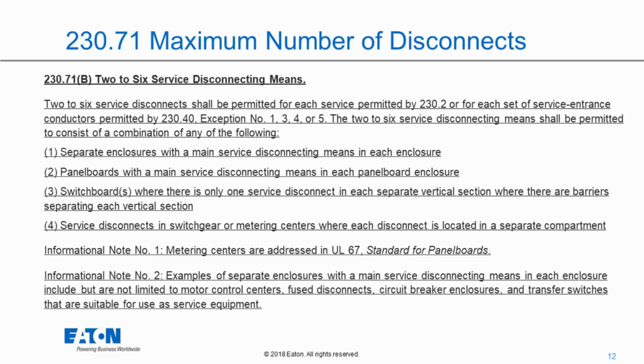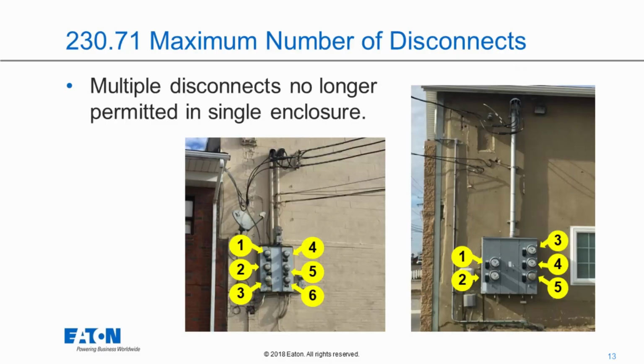And then with regards to list item 1, they give an example of separate enclosures with a main service disconnect. Could be, but not limited to, motor control centers, fuse disconnects, circuit breaker enclosures, and transfer switches that are suitable for service equipment. So this is a very common scenario. I mentioned earlier about the meter centers. It was very common to perhaps just come into a pull section, an incoming terminal box pull section in the middle of that meter center, and then as you can see here, you have up to 6 tenant mains. And as mentioned, this would no longer be permitted.